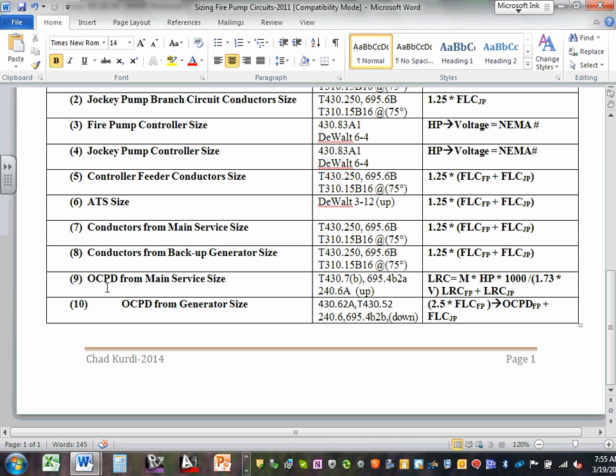So you go to 9. 9 is the overcurrent protection device from the main service side. How do you size it? Here are all your references in the NEC code book from Article 695 that talks about fire pumps and other articles. We size the circuit breaker from the utility side, guys, based on the locked rotor current. LRC is locked rotor current.